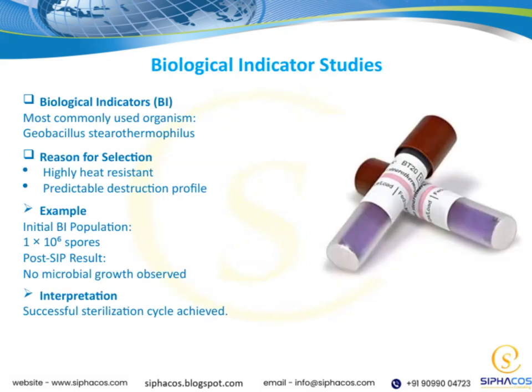Let's talk about biological indicator studies, a key way to verify sterilization. We use biological indicators, or BIs, which contain a specific organism. The most common one is Geobacillus stearothermophilus. Why? Because it's highly heat-resistant and has a predictable destruction profile. For example, we might start with 1 million spores. After the sterilization process, no microbial growth is observed. That means the cycle worked, sterilization was successful.